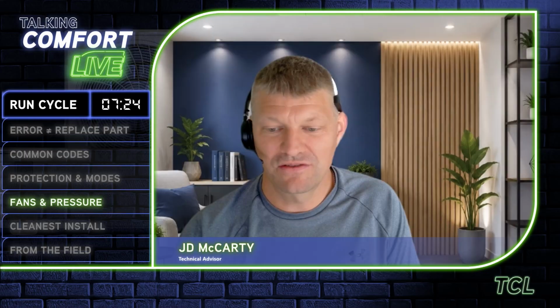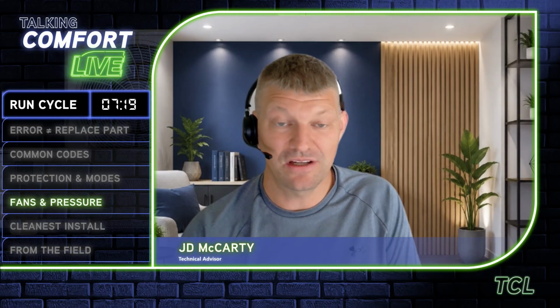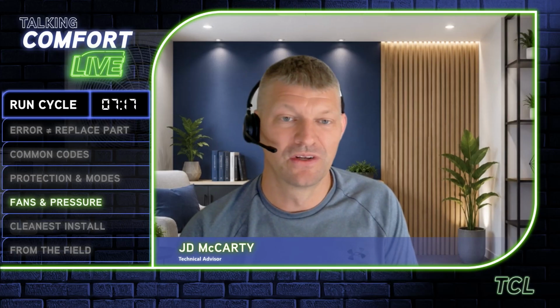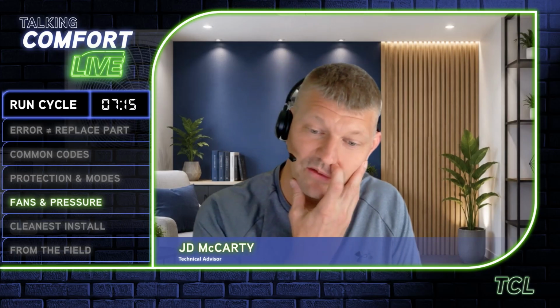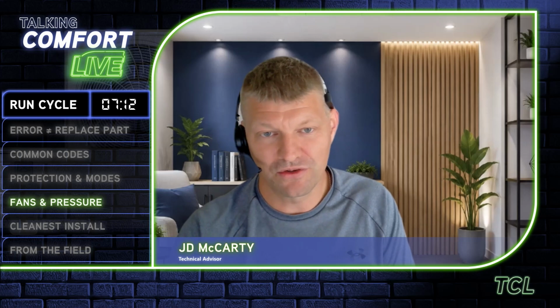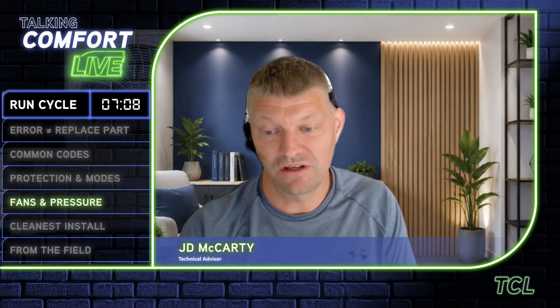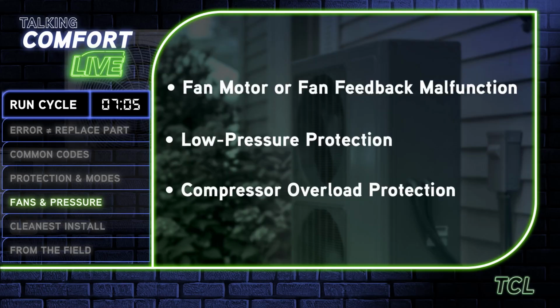So, two little things on the H3 code. One of the calls I get a lot with the H3 is they have loops in the line set, and then the smaller BTU units don't have the umph in the compressor to push through those loops, and it causes that compressor to go into overload protection, and we get the H3 code. So that's a big one there. And then on new installs, if you get an H3 code, I would make sure that you opened all your valves. I get that call often too.